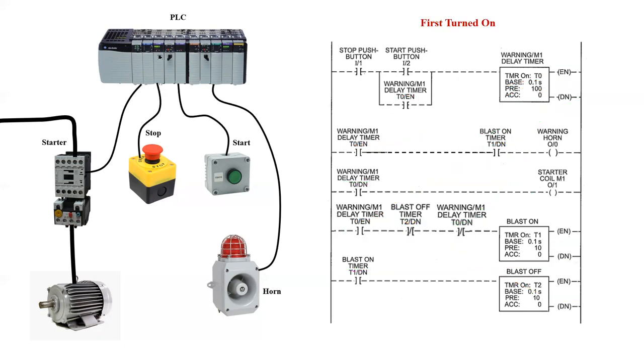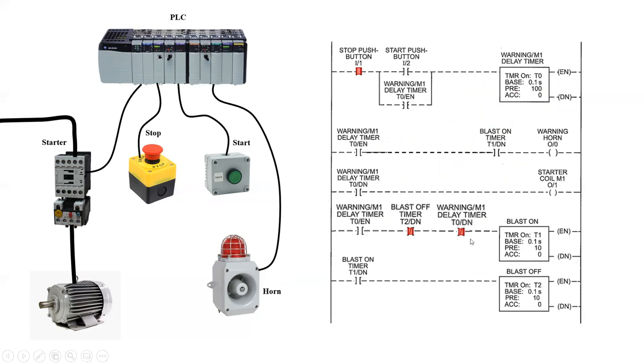Let's see what happens when we first turn on the system. We have a stop push button, which is connected to input one, which is an examine if on input instruction. This would mean that the stop push button has this input one true. We then also have two separate internal bits that are examine if off. Both of these internal bits, being that they're examine if off, mean that if the item that controls them is off, they will be true.